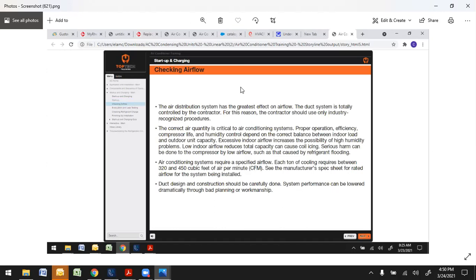Now, airflow is critical for all new systems. It doesn't matter the brand. The air distribution system has the greatest effect on airflow. The duct system is totally controlled by the contractor if you designed it, or if it's existing, it's with the house. For this reason, the contractor should only use industry recognized procedures. The correct air quantity is critical to air conditioning systems: proper operation, efficiency, compressor life, humidity control, and outdoor unit capacity.